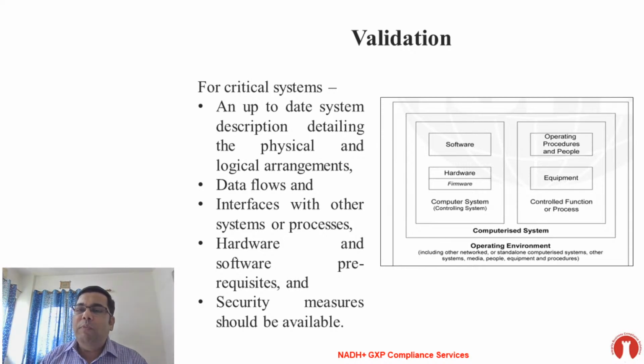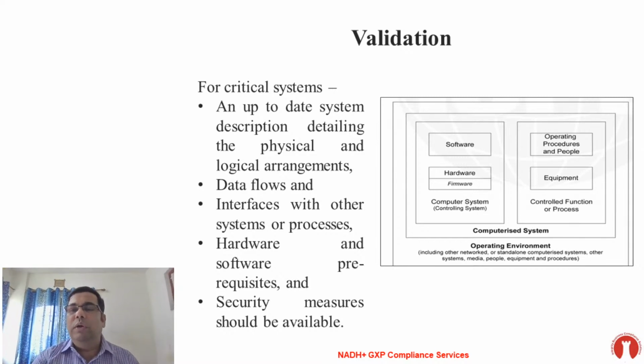Challenge study should be performed for each new instrument with the software control. It depends on what its impact is. If you change or upgrade your instrument, what is its impact on the software? If there is no impact on the software, then I don't mind, but you have to evaluate whether it is impacting or not. So don't worry about that. I just gave short information about this question. Tomorrow we will discuss in more detail about that.